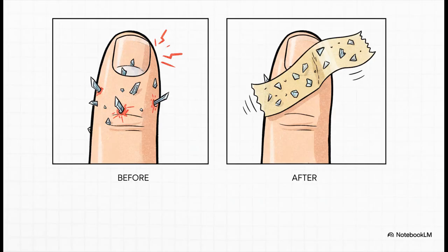Now, here's a detail that really just brings the human element into all of this. Those tiny little scraps of leftover fiber, they're like microscopic glass needles. They are so sharp they can easily get into your skin and you'd never even feel it. The standard actually tells technicians they have to clean them up by dabbing the area with the sticky side of tape to make sure no dangerous little slivers are left behind.